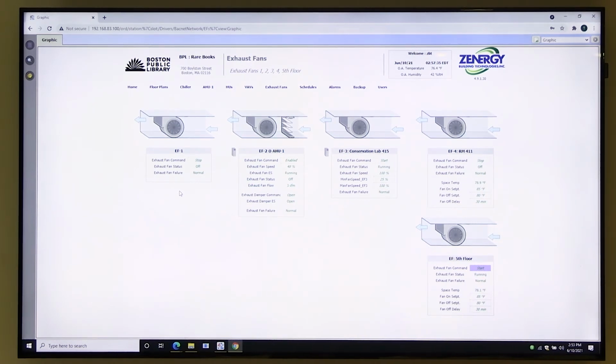EF3 is basically the lab exhaust for that conservation room. So there's a fume hood and an exhaust damper, and EF3 is what's actually pulling the air out of that space. Are those controlled by timers? Is it controlled by the EMS, or is it occupation? Yeah, that's a good question. Would that space be 24/7 exhaust? It'd be a waste of energy to just be pulling conditioned air.